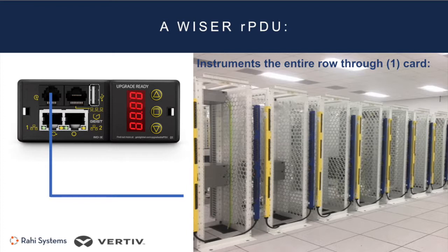And one way a PDU can do this is by plugging in external sensors to help a user understand the wider data center ecosystem. So we know that power and cooling have a very close relationship and are intertwined in computing spaces. So installing temperature sensors to this particular PDU or environmental sensors would certainly add value to that particular user so they can see how power and cooling in their particular instance are interrelated. It helps the user better understand, again, what's happening in the facility.